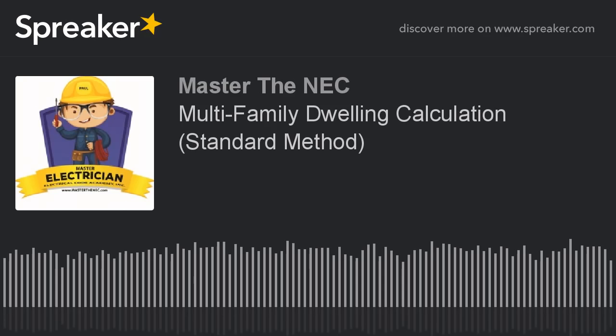We're adding up all the general lighting loads together right here, and this happens to be really a receptacle load, but you can see that it's an actual load, so it's getting added into this value that we're going to add all together here. So, laundry load, at least 1. If there was more than 1 laundry circuit, and I wouldn't imagine so in a 1,000 square foot unit, it would be 1,500 for each.